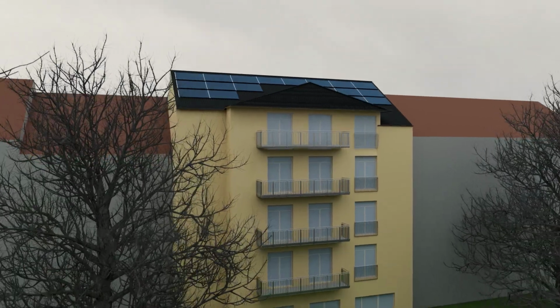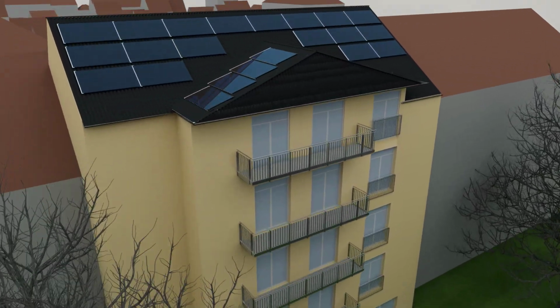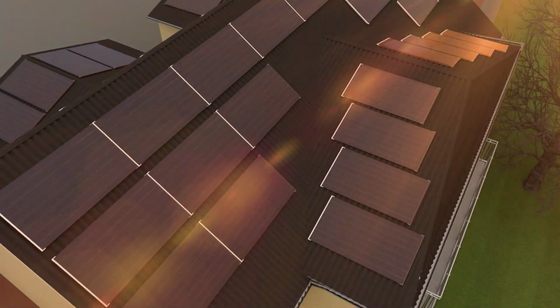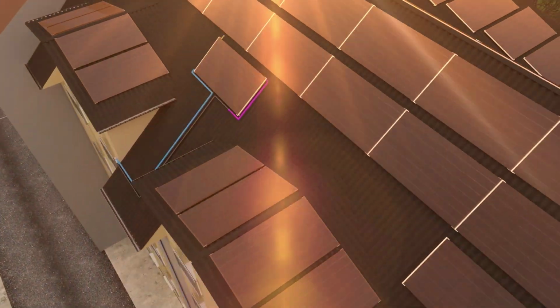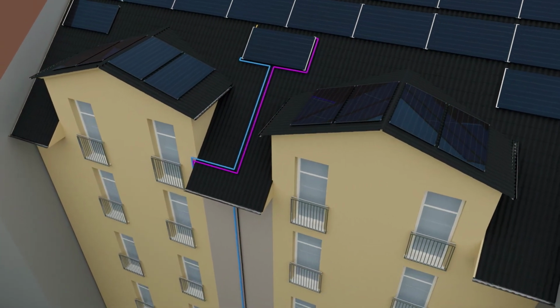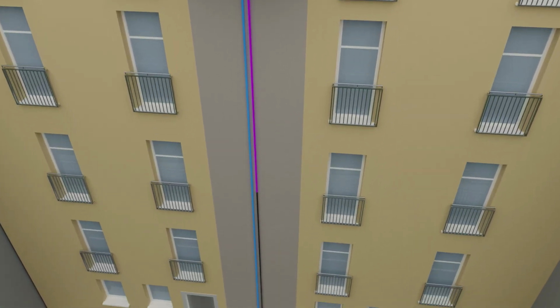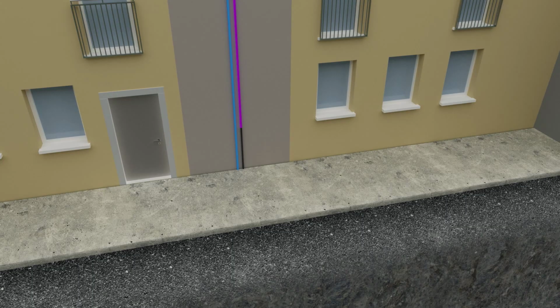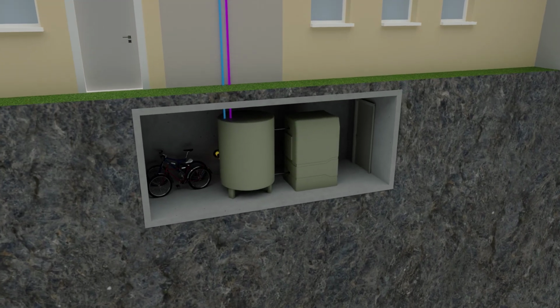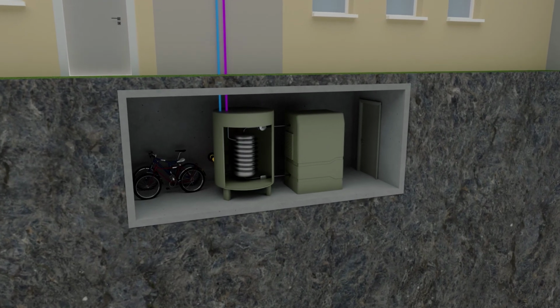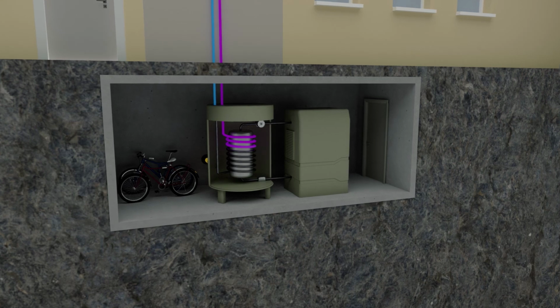There are even more advantages to such an innovative system. On a partly sunny day in November, for example, a regular solar panel can barely use the heat from the roof. However, the heat pump now raises the temperature of the brine from the roof, approximately 20 degrees Celsius, to heating temperature.